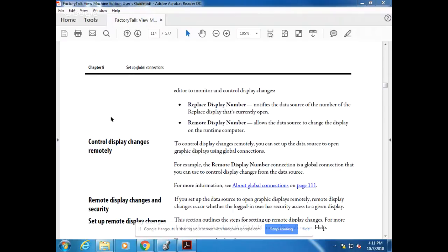The runtime file on the newer versions of this, I forget 5 and above or 6 and above, you can download that MER file and restore it and open it. However, there are a few things that don't come in. One of them, if I remember correctly, being the security passwords that allow you to access the screens. You can fix that. You just have to go enter new passwords, but you download it and you can't get to stuff because the passwords aren't in that system.